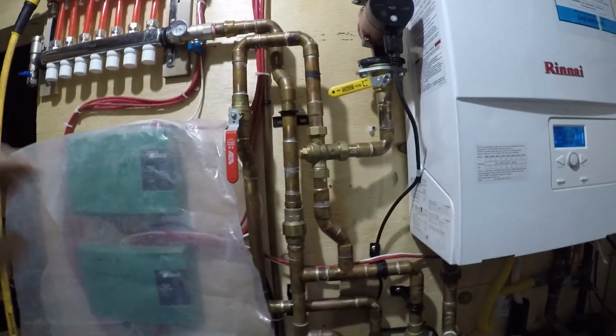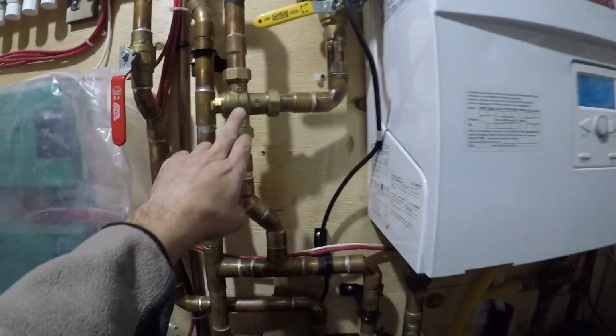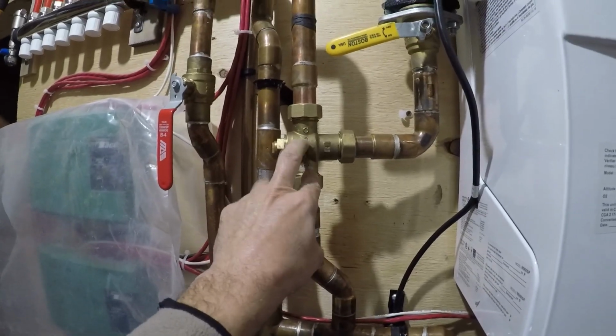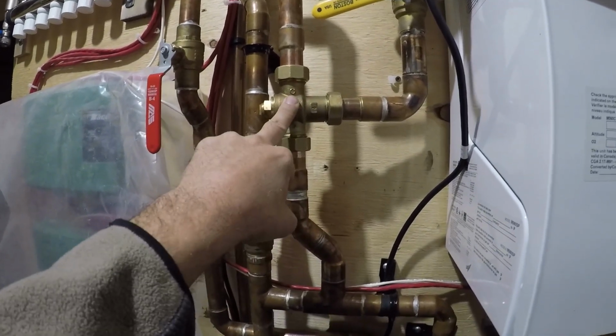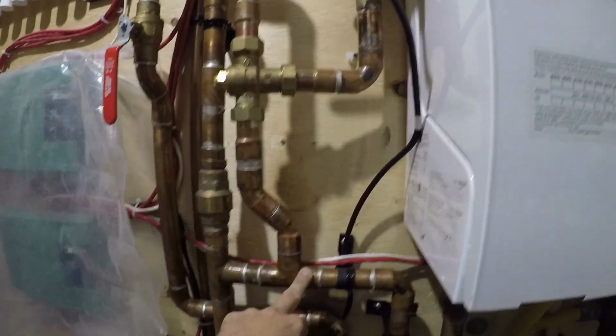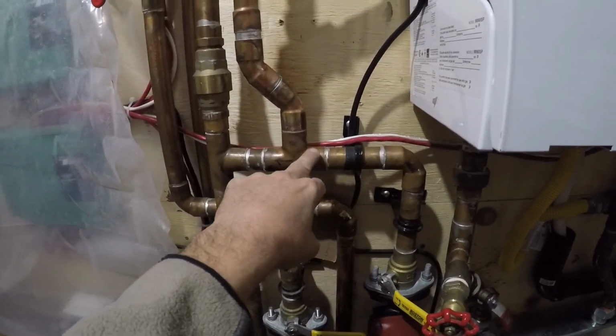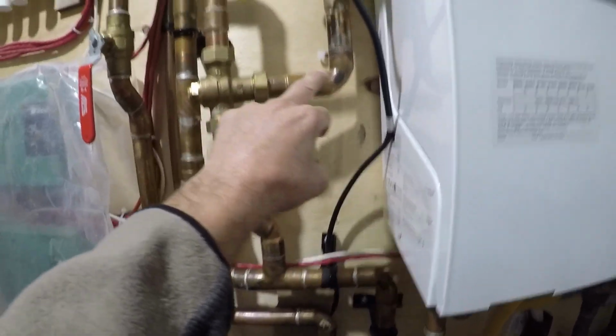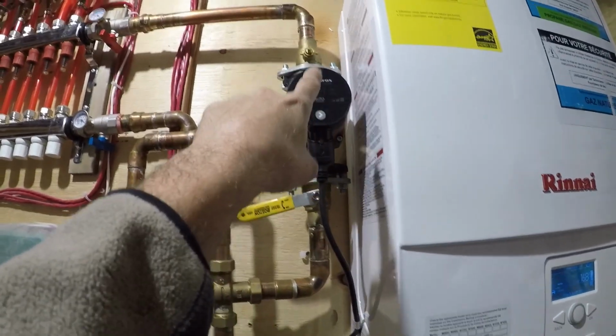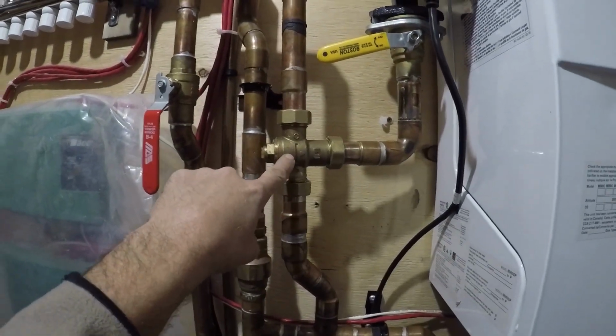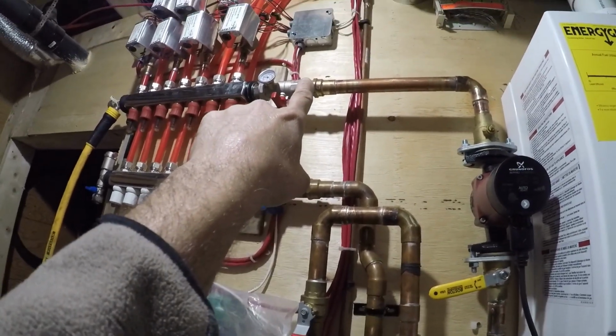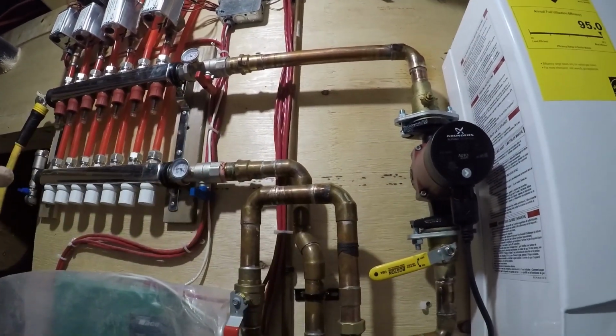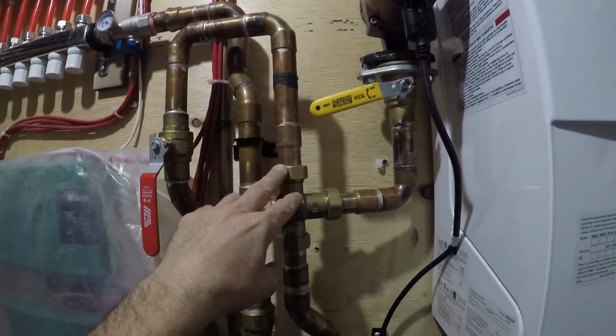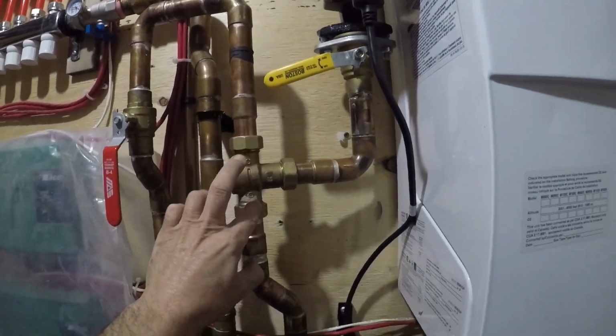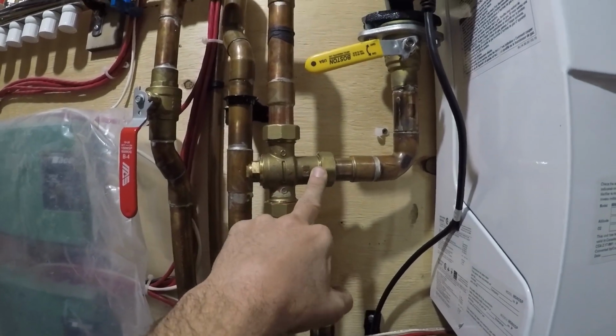Basically, back when I designed the system, there's these thermostatic valves here. You see them on your hot water heaters a lot. So basically what it does is it takes the water, so our system here, the water gets pumped up here, and then goes through the circulator pump and out to all the zones. The problem is, the way I had this hooked up before, this valve was up there, and the pump would push the water through it, and these valves don't work that way. These valves have to have the water sucked through it in order for them to function.